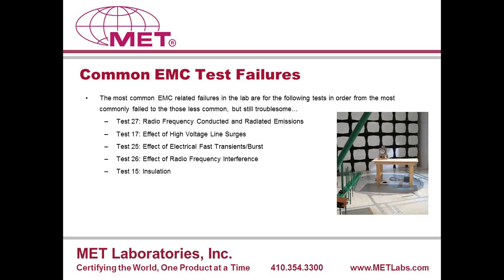The next common failure we see is test number 17, effect of high voltage line surges. So although it says effect of high voltage line surges, this test typically comprises two different surges. One is the combination wave surge, which is simulating a lightning strike and the transients that are induced because of this lightning strike. And the second surge test is a ring wave surge test, this type of transient is caused due to switching of loads, switching of reactive loads. So these are the two types of surges that we are required to test. The other important thing to note is that for this test, the test amplitude is 6 kilovolts, which is really very high, because the other common commercial tests that we perform only go up to a maximum amplitude of 4 kilovolts. So that is something that you should consider.